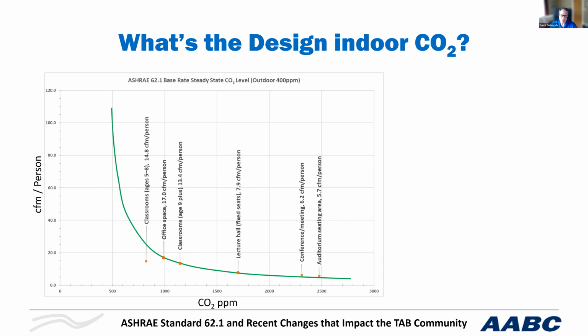So they are significantly different, because there are a lot of orange dots that don't line up on 1,000, as you notice. And you can also see that the first dot all the way to the left is for classrooms, 5 to 8 years old. That completely falls off the curve because their generation rate is much different than an older teenager or an adult. And this curve that I drew is specific to adults ages 30 to 60, 50-50 male, female, with a mean body mass and low activity. You're basically sitting, working at a desk, which is about 1.3 Met. It's also based on 70 degrees and sea level, because there is a temperature and barometric density effect on CO2. CO2 sensors have to be adjusted for elevation, just like an airflow measurement.